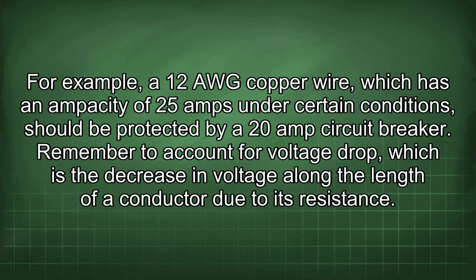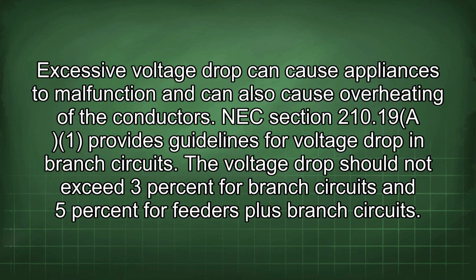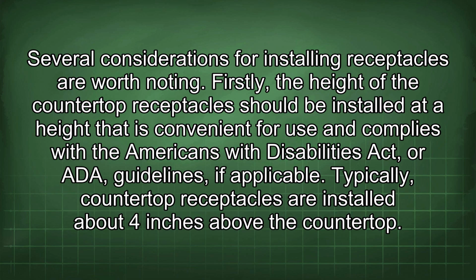Remember to account for voltage drop, which is the decrease in voltage along the length of a conductor due to its resistance. Excessive voltage drop can cause appliances to malfunction and can also cause overheating of the conductors. NEC Section 210.19(A) provides guidelines for voltage drop in branch circuits. The voltage drop should not exceed 3% for branch circuits and 5% for feeders plus branch circuits. Several considerations for installing receptacles are worth noting.